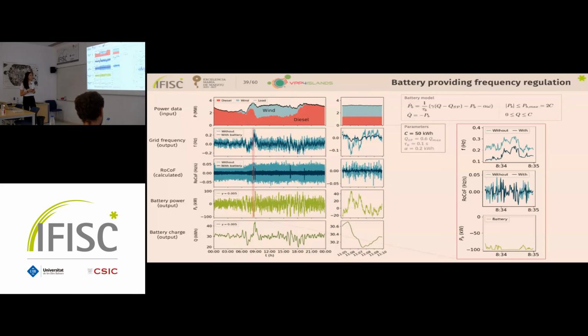If we zoom in on one of those peaks, we can see that the battery is now at its limit, so it cannot absorb any more power. Because of that, the frequency fluctuations are exactly the same as in the case without the battery, but they are simply shifted, and because of that, the ROCOF is exactly the same.